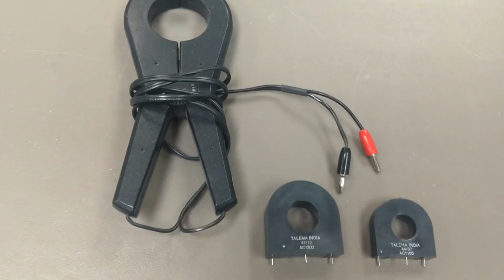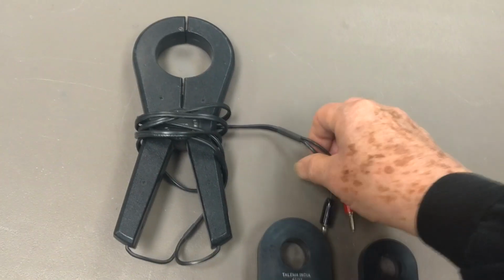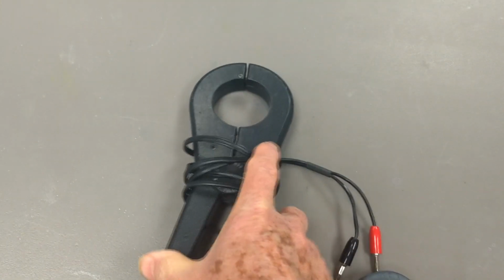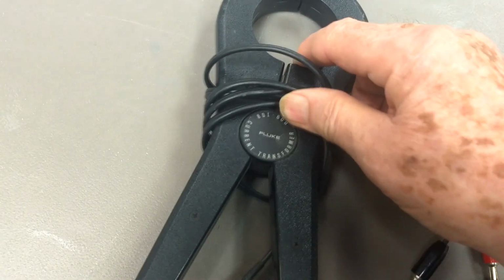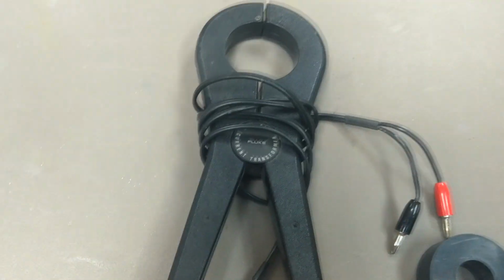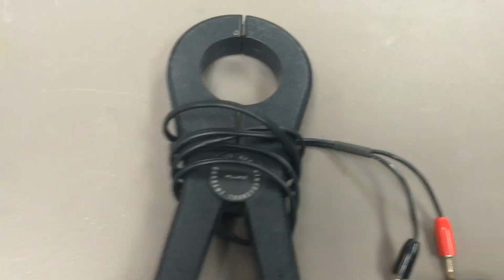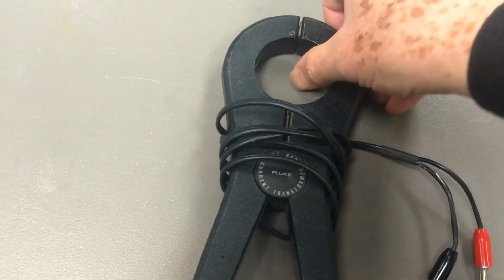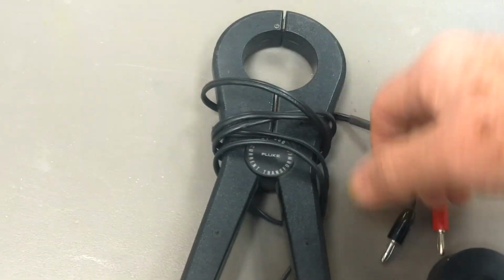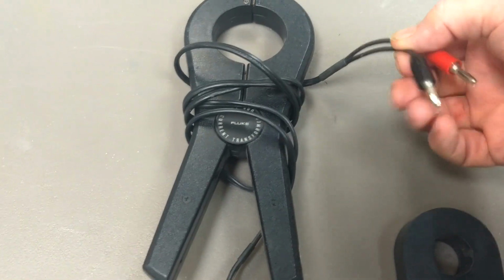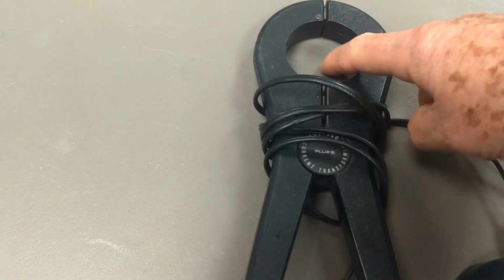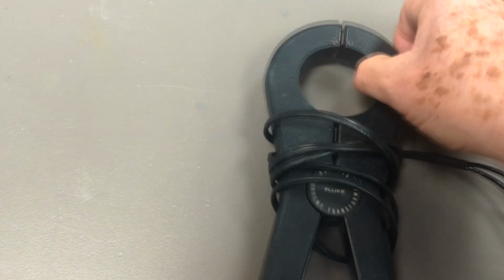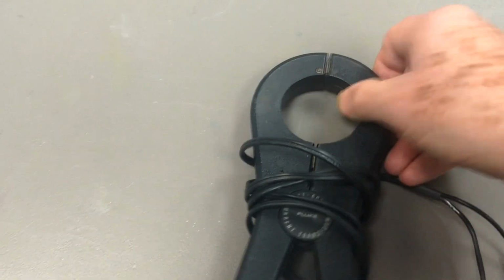Here's some examples of current transformers. This one is made to plug into a multimeter, and it can be clamped onto a current carrying conductor, and it has a ratio of 1,000 to 1. So there's 1,000 turns on the secondary, and typically there'd be a single turn on the primary. The wire would go through here. So reading 1 milliamp on the meter would mean 1 amp going through here. Of course, you can also pass a wire through here several times if you want to measure lower currents.